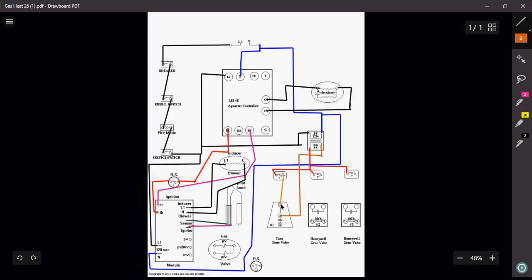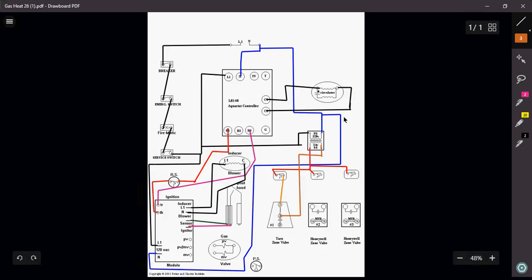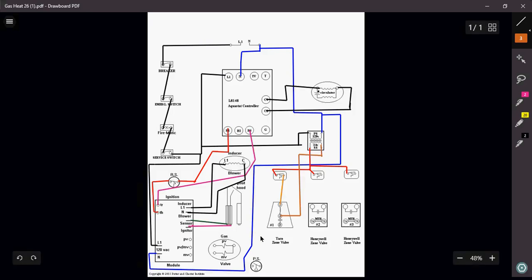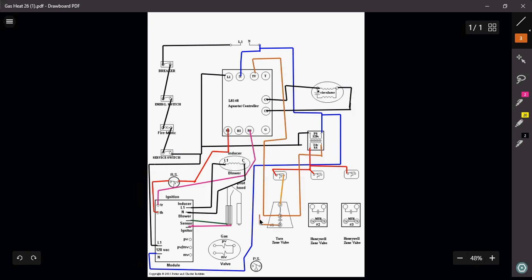Because now there is that one circuit right there. My thermostat, the terminal one, through my motor, and then back. Source, path, switch, load. Right there. So now that that is complete, I have to send that. Remember, I have to send it to two separate places. I have sent it back to my common on my transformer, but I also have to send it up. Oh, you guessed it. I got to send it all the way up to one of my T's on my Aquastat. My other, my last terminal on my TACO zone valve is going to go to my other T on my Aquastat. Just like that.